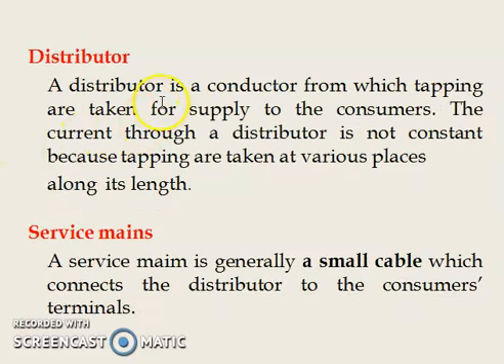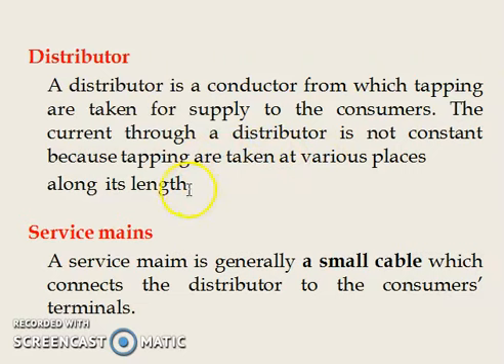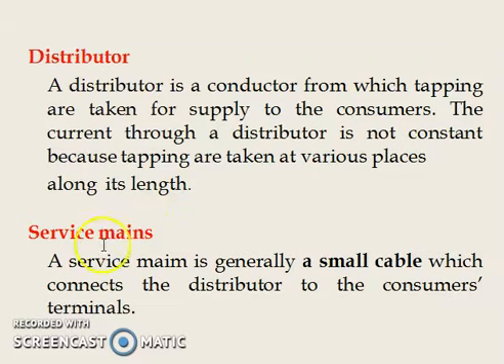A distributor is also a conductor, but tappings can be taken from it at various places along its length, and it is connected to the consumers. The current through the distributor is not constant because tappings are taken. The design consideration for a distributor is that voltage has to be maintained constant.